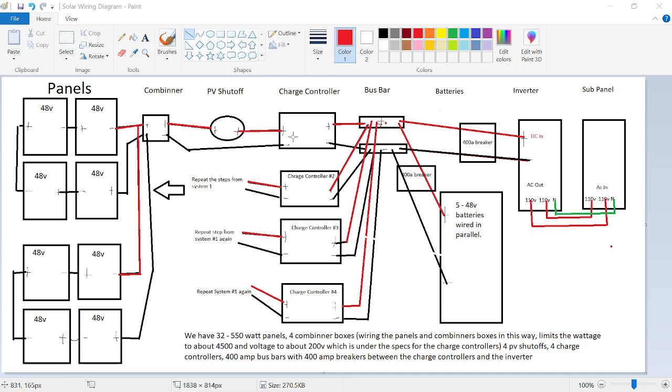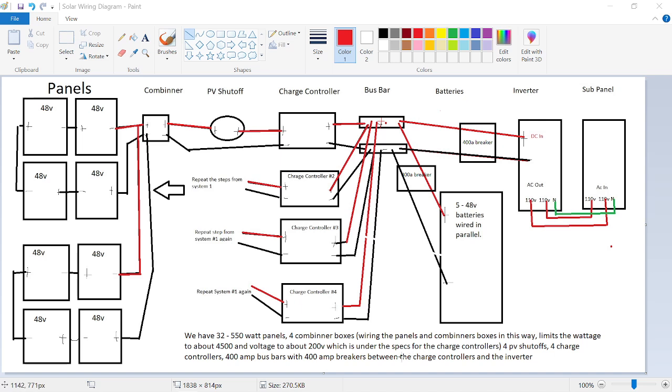So then we get into the charge controllers. We have four of those. Our charge controllers are max 250 volts and 5,200 watts. So with the way I wired these panels and the combiner boxes, we have about 4,500 watts input at the peak of the sunny day and about 200 volts. So we have some leeway so those combiner boxes don't get so hot when they're actually restricting the power when the batteries are actually full.